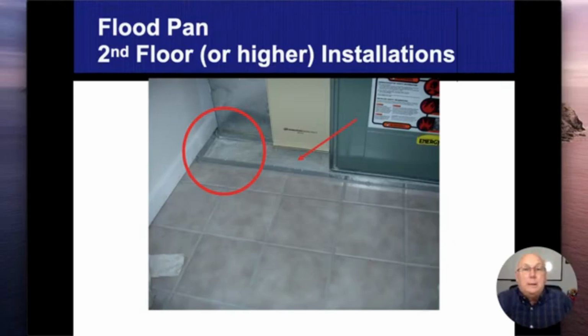Pans. The only time we do not have to have a pan underneath the furnace is when we're in a basement or a concrete floor underneath, and there's no chance of doing any damage below the structure. But if there's wood frame or something like that, or it's on an upper floor, we want to be able to collect water from the high efficiency furnace, the humidifier, and the air conditioning unit. All those items can go ahead and create water, and if the condensate drains clog up, then we need to keep that from damaging the rest of the building.